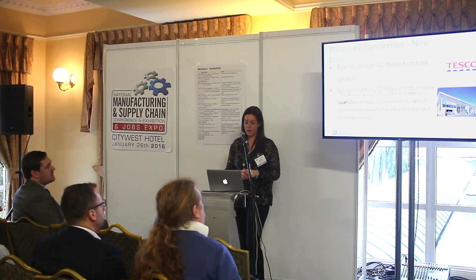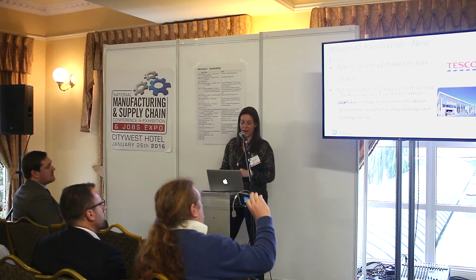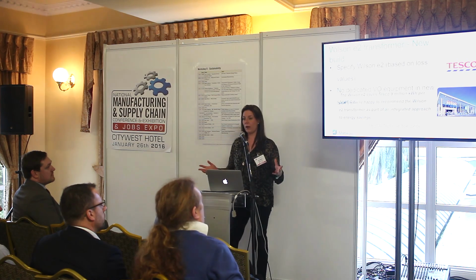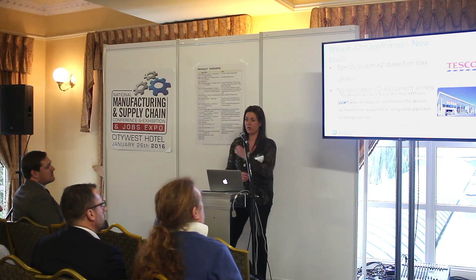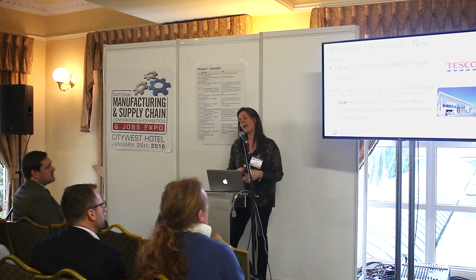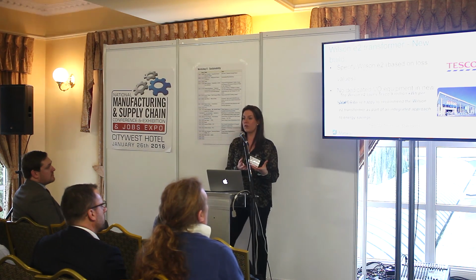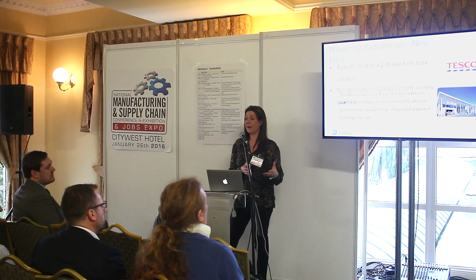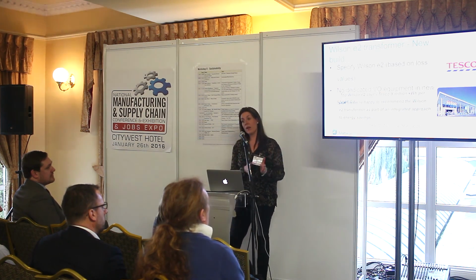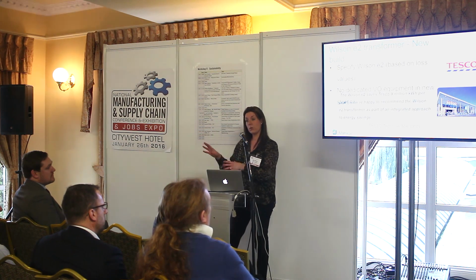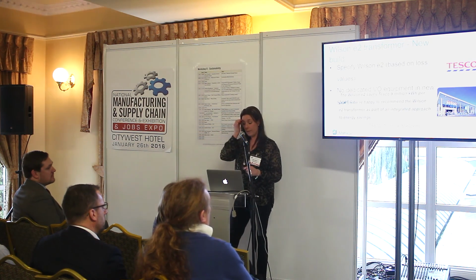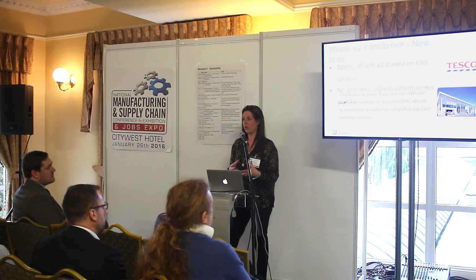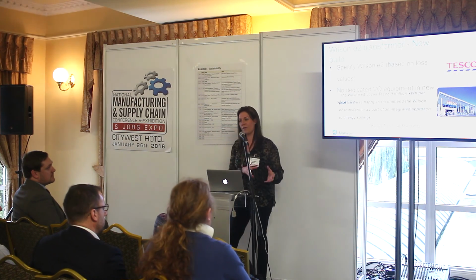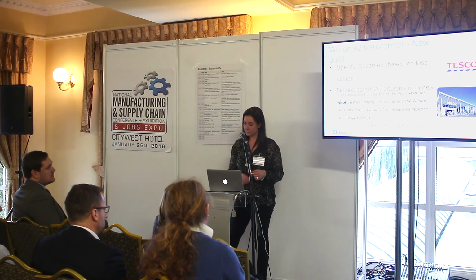Looking here at the situation with Tesco, they had quite a large-scale rollout programme to do voltage optimisation across the system. And what we explained to them was that the transformer would do the job. In those stores that were supplied at medium voltage, they will put the Wilson E2 in. And then at the low voltage stores, which are the little ones on the street side, they would actually fit a low voltage optimizer. So it's not that I'm saying that there's not a place in the market for those products, but not if you have your own transformer.